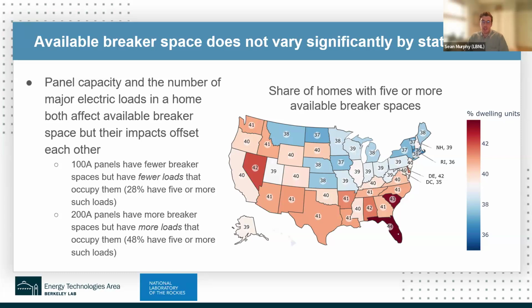The reason we don't see as much variation is that there are countervailing effects of panel capacity size on breaker space and the impact of the number of electrical loads on breaker space. The intuition is that you may have a larger panel, giving you more space, but oftentimes a large panel also comes with more loads, so you start with more space but end up using more of it. In places with smaller panels, there are fewer large loads, so you're using less of the breaker space provided. As a result, there isn't a large difference across the country in available breaker space.